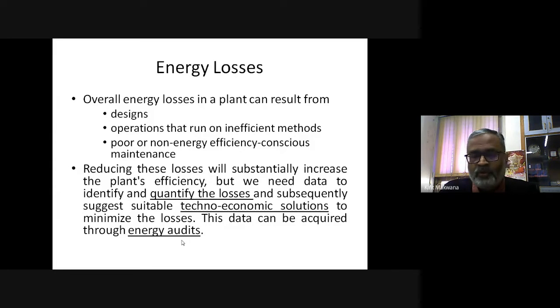Now, when we checked that motor on full load, it was taking 35 ampere of current. While the wire was not connected, when they were not stretching or pulling the wire, it took 32 ampere of current. And the operator was proud that without the load it takes 32 ampere, and with the load it takes just 3 ampere more, and the work is going on. So our motor is very efficient.